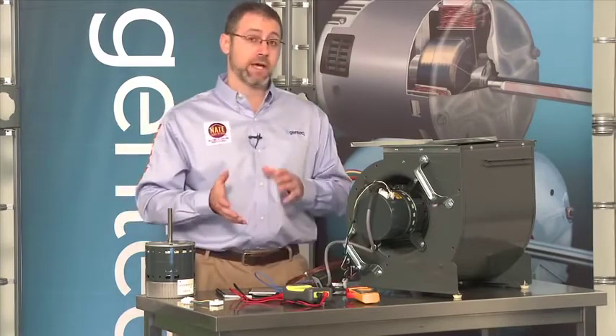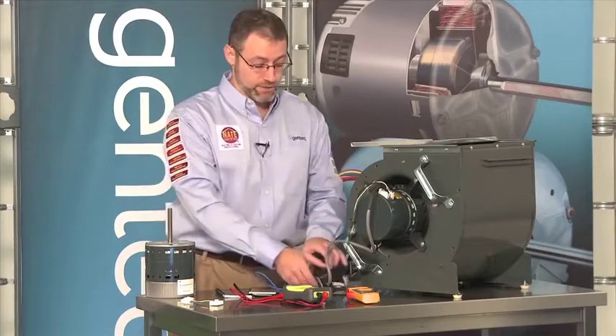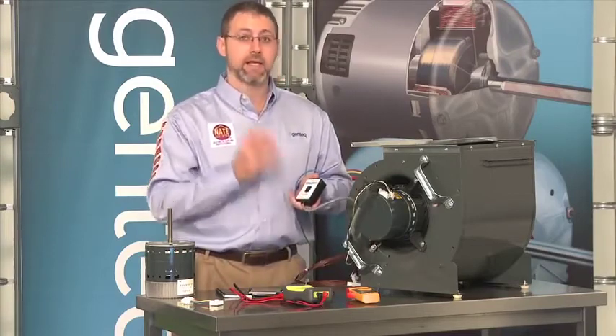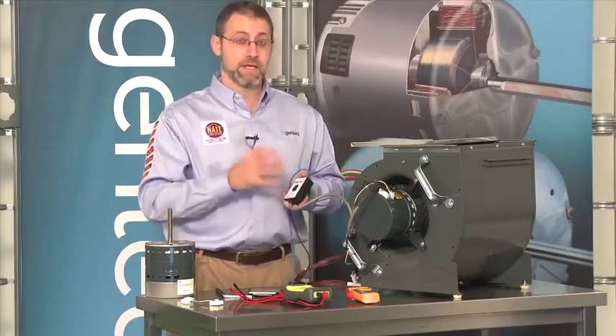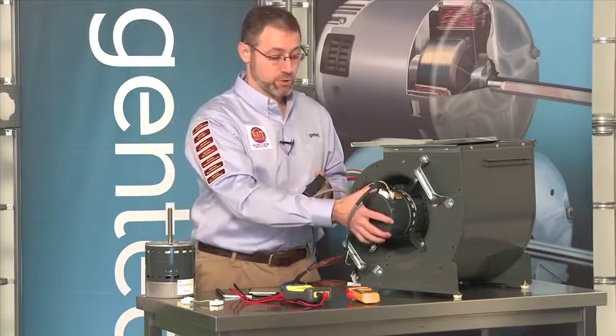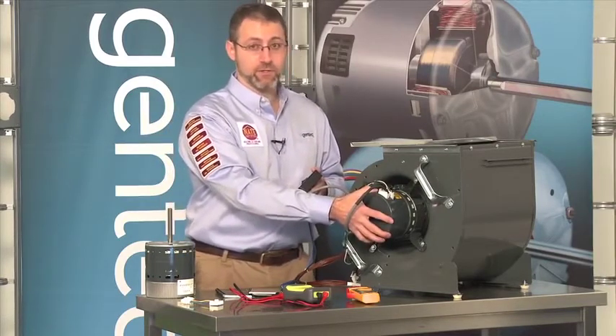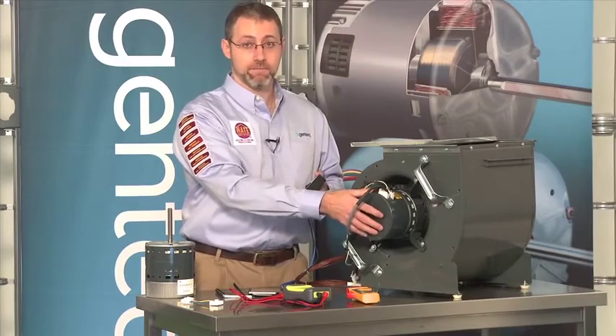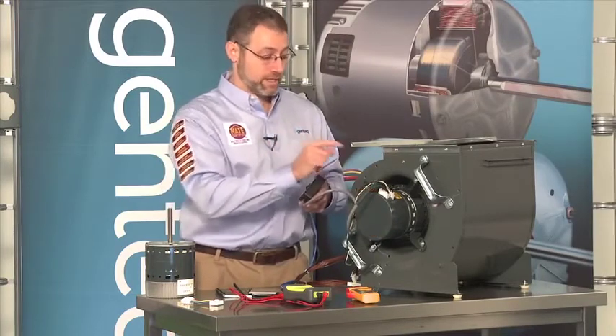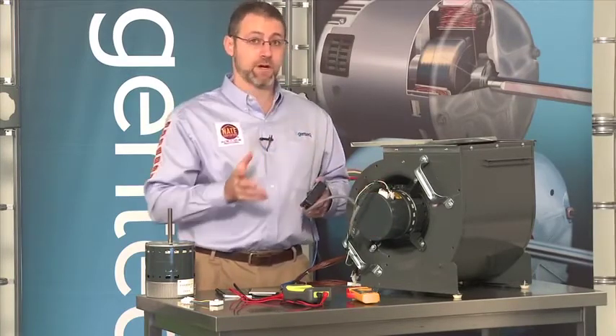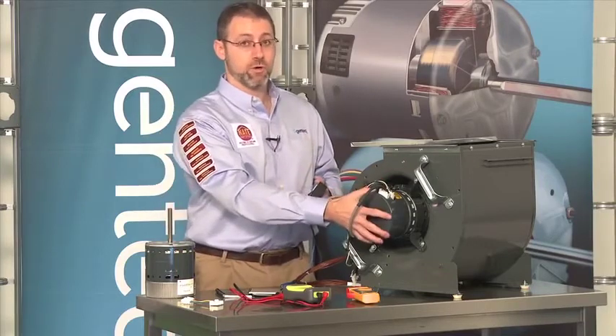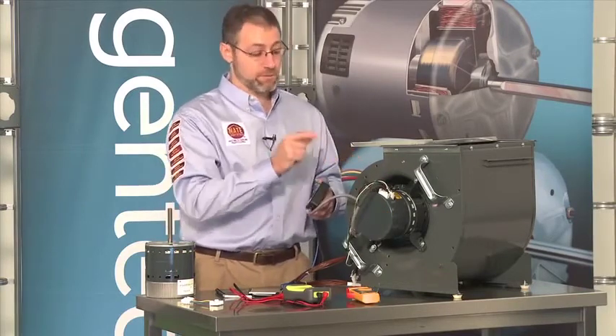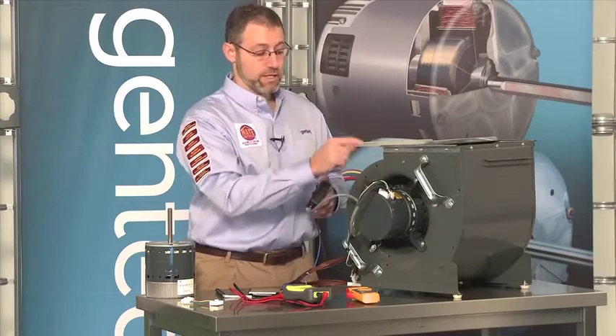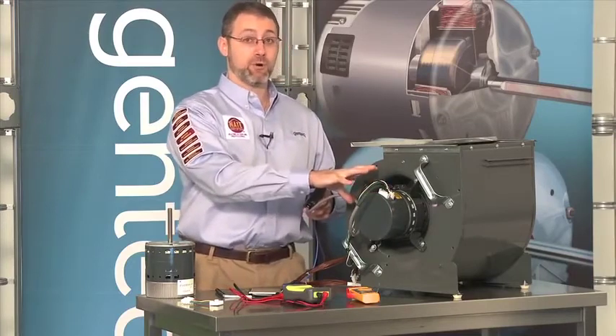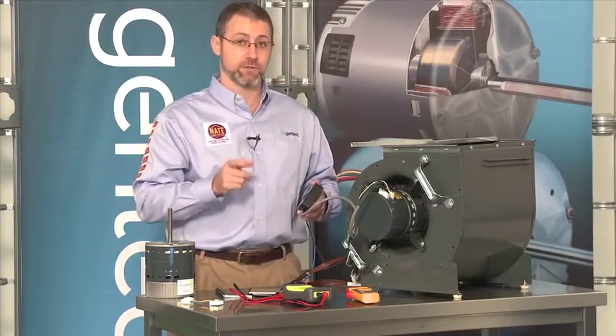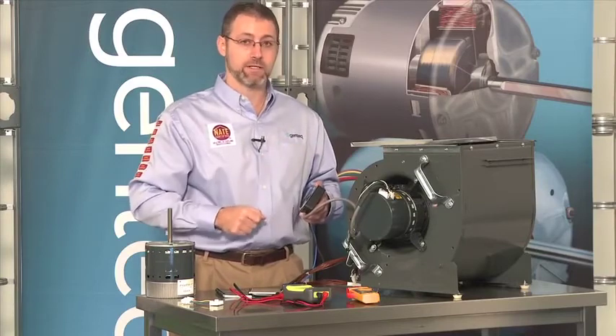So let's look at the other scenario. The other scenario is I flip the switch on the TechMate and the motor does not run. In this case, I have proved that the control, the microprocessor end of the motor, is no good. However, what I don't know is whether the motor is any good, because with variable speed motors you can replace the control separately from the motor. So before we can remove the control and check the motor, we have to turn the power off and wait 5 minutes. So we'll do that now. When we come back, we'll go ahead and diagnose the motor.